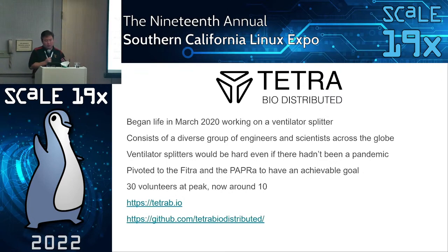The other thing is that we made this so that it'd be printed on FDM or FFF printers. So the design choices that we made for it to be printable are different than what you would want for an injection molded or some other more commercial housing. You also have to take into account the nuances of the printing technology in developing the plastic pieces, like orientation of print and the thickness of walls in terms of what you can get out of your nozzle. We've done a lot of iteration on that to try to get a consistent print that works.